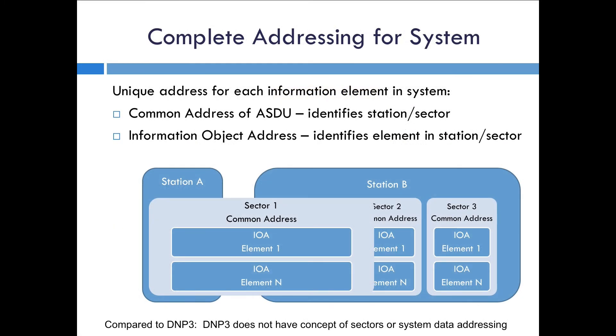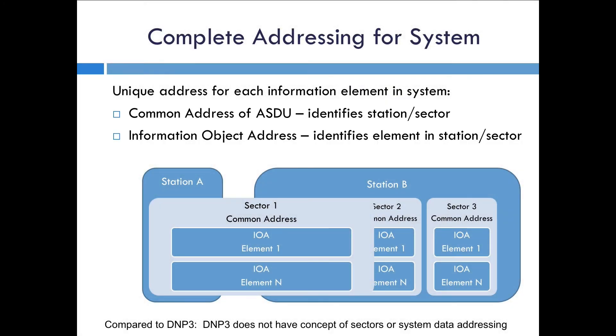The complete addressing for the system uses the common address together with the information object address, or IOA. For example, one station could have just one sector while another could have multiple sectors. Each sector has a common address, and each element has an IOA. The combination of common address and IOA gives a distinct address for every object in the system. This is different from DNP3, where the address number is reused for each data type and uniqueness comes from data type plus index number, whereas in IEC 60870-5 it's based on the common address and the IOA.